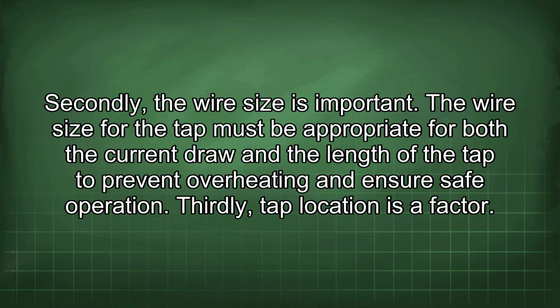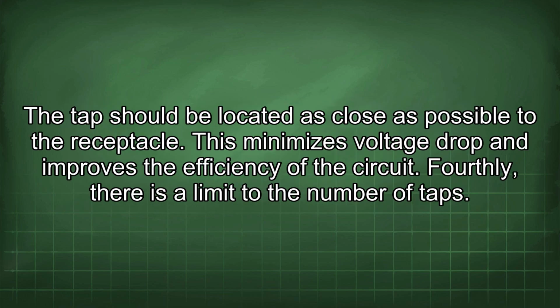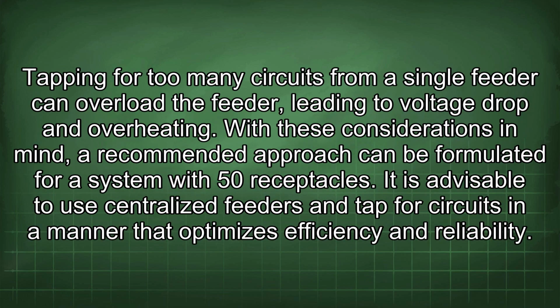Thirdly, tap location is a factor. The tap should be located as close as possible to the receptacle. This minimizes voltage drop and improves the efficiency of the circuit. Fourthly, there is a limit to the number of taps. Tapping for too many circuits from a single feeder can overload the feeder, leading to voltage drop and overheating. With these considerations in mind, a recommended approach can be formulated for a system with 50 receptacles.